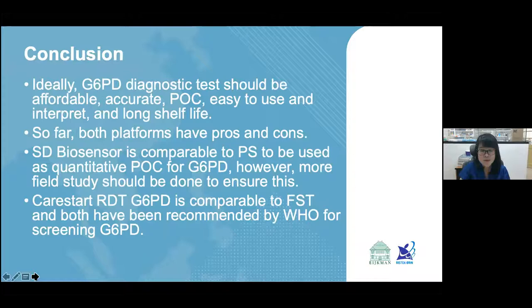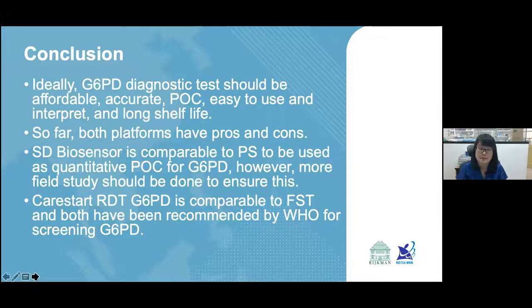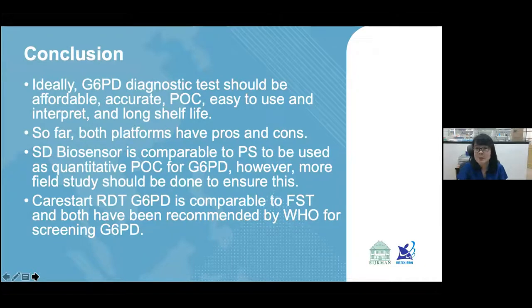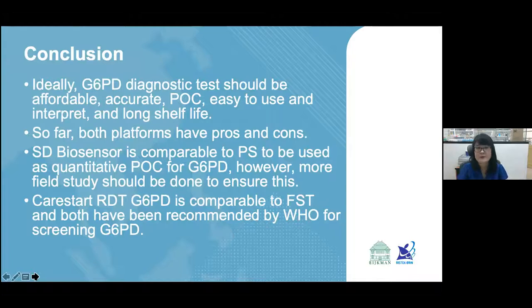In conclusion, ideally we would like a G6PD diagnostic that is affordable, accurate, point-of-care, easy to use and interpret, and has a long shelf life. Both quantitative and qualitative platforms have their own pros and cons. The SD Biosensor is comparable to Point Scientific as a quantitative point-of-care test, though more studies should be done. The CareStart RDT is comparable to the FST, and both have now been recommended by WHO for screening G6PD.